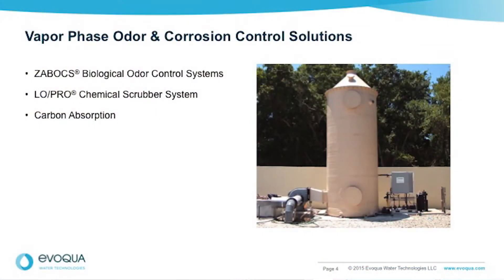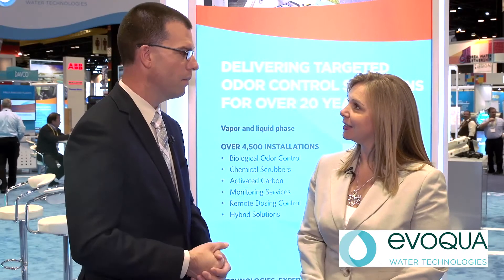Sometimes what you want to do is control it in the air — collect the air in the headspace of unit operations, pull a negative draft on those areas, and filter the air so it's discharged clean. For that, we use biological systems, our ZABOCS biofilters and biotrickling filters. We use chemical scrubbers like our LowPro, and also carbon adsorption. So we have a wide spectrum of ways to attack the problem.